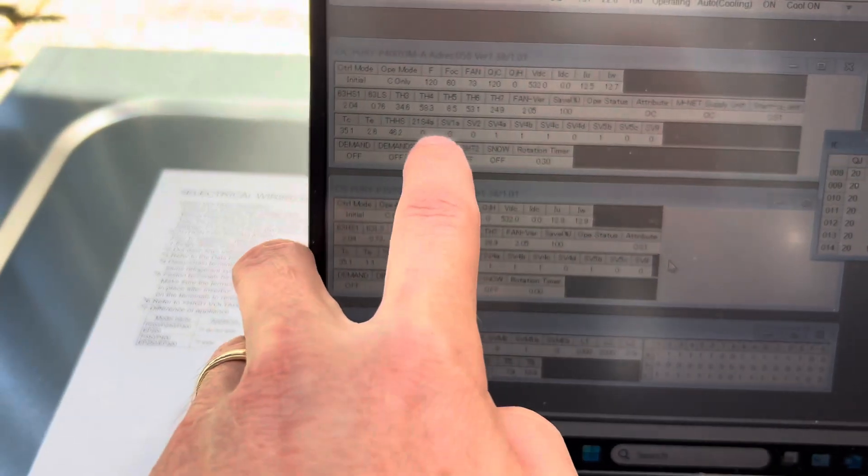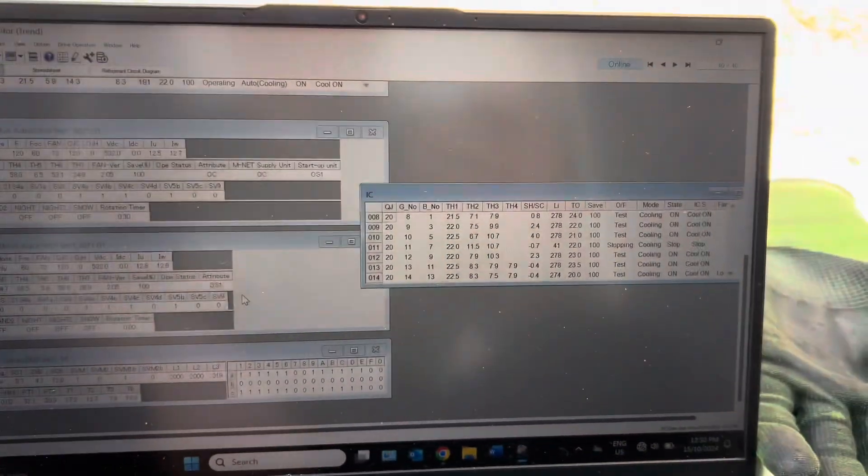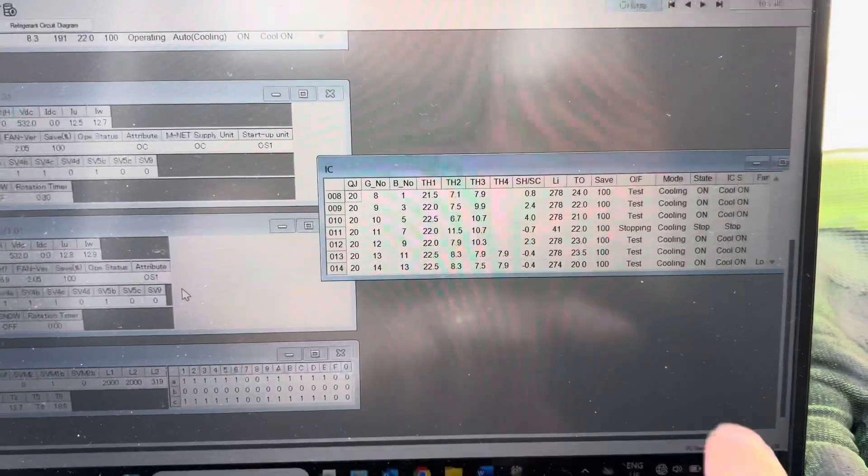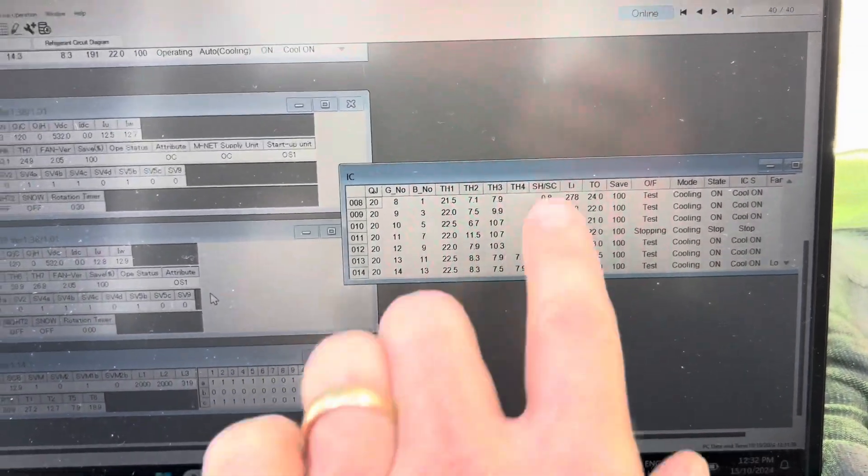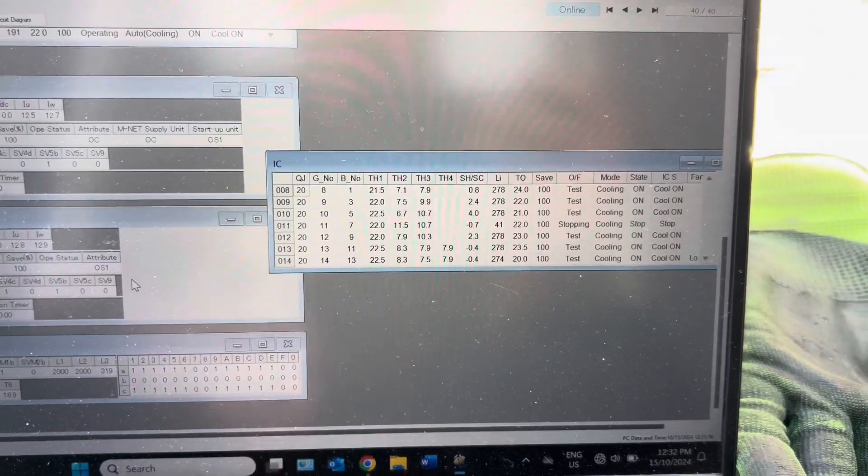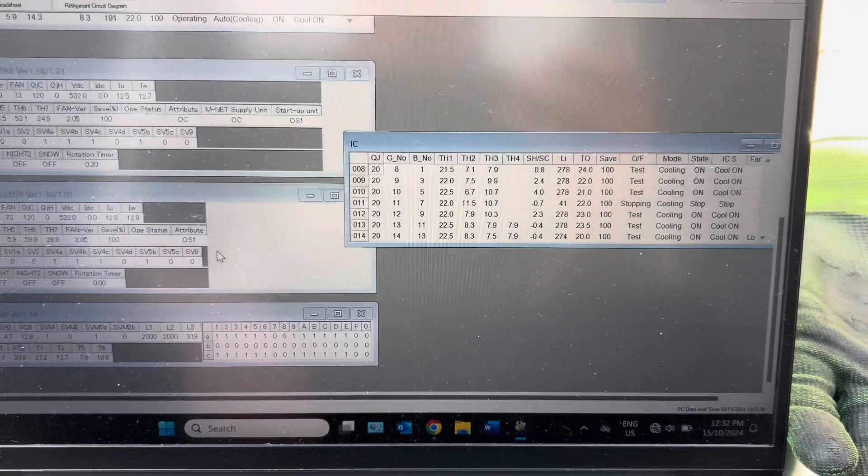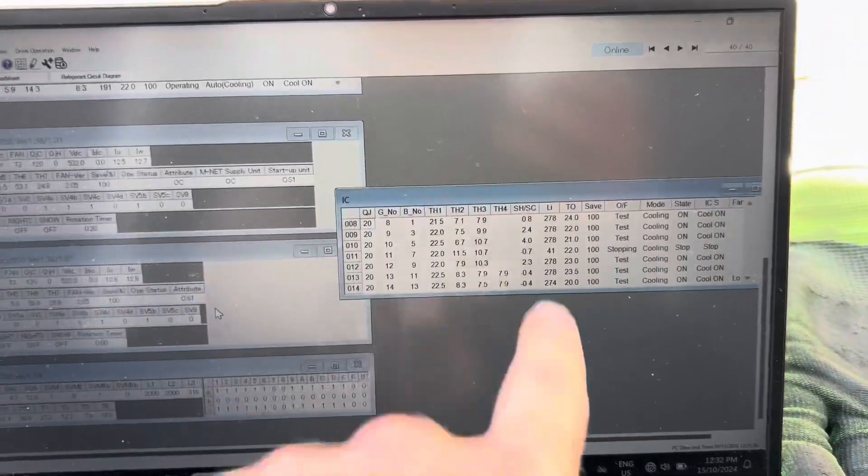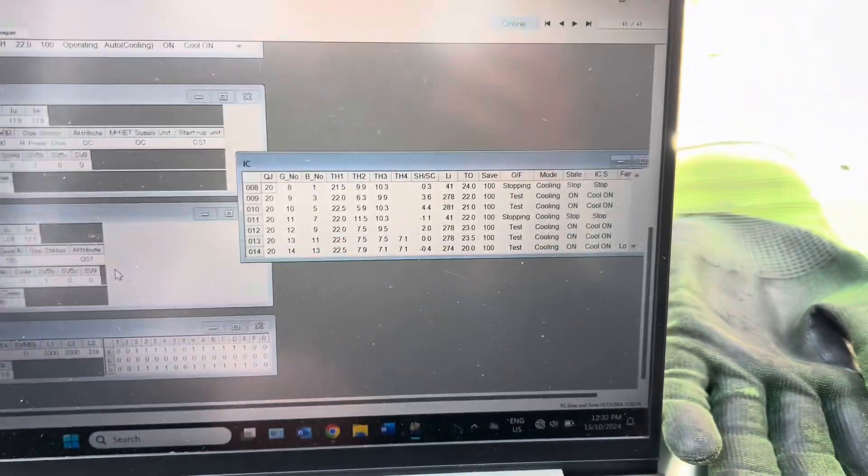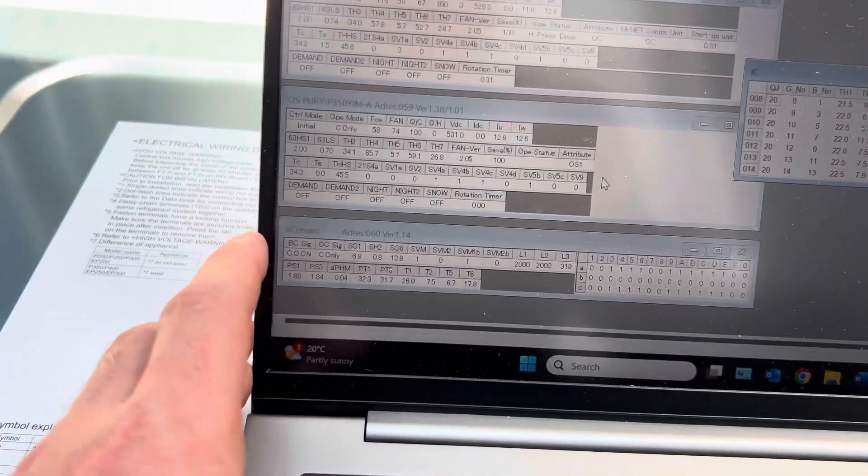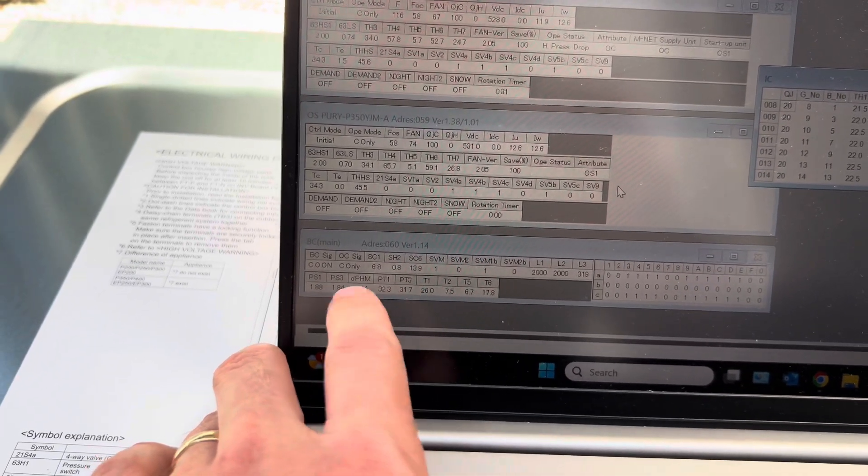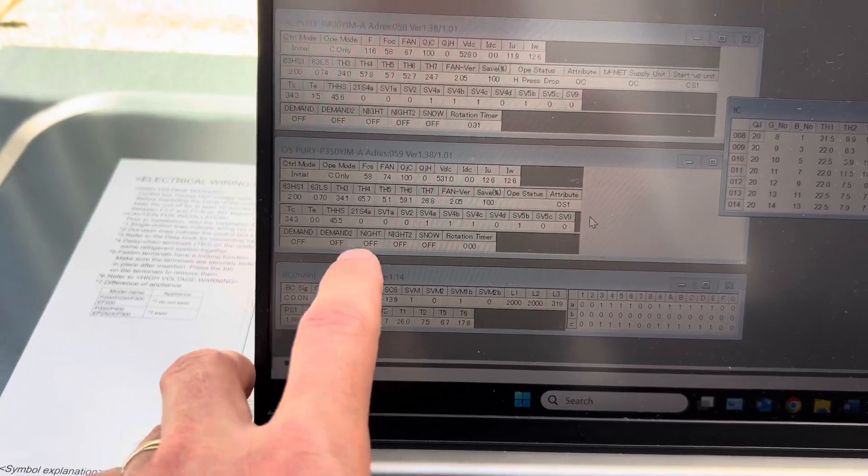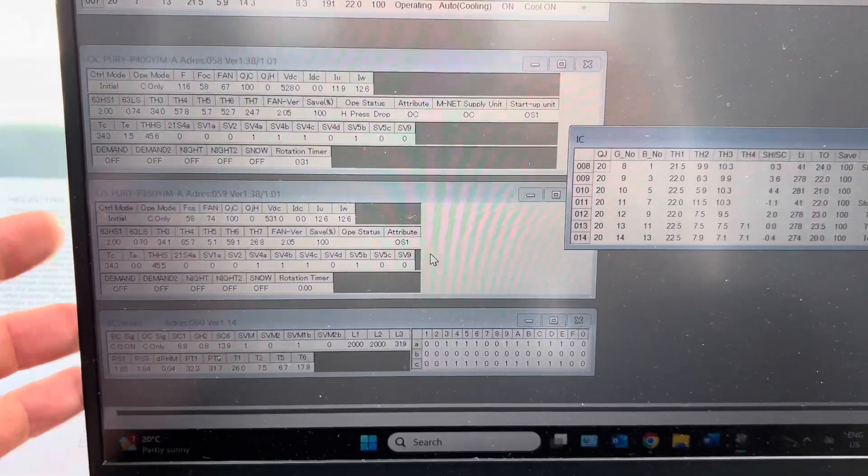You can see here TH5, which is our accumulated inlet temperature, not suction, just pre the accumulator. It's still reading quite high, but SV1A, which is the oil return solenoid, is still open, so usually you'll see that when it's quite high. You can probably hear that hissing noise, that's it. So for the first four minutes of operation that will be running, or if it feels like it needs to because our suction pressure drops. The system's still in initial mode too, so just waiting for it to come out of that before I fully start diving into the data that's coming through. Keeping an eye on it, everything looks okay at the moment, but yeah, we'll just wait for it to come out of initial mode. You can see now SV1A has closed, and TH5 has come down to 6.5 and 5.9. People are starting to get a little bit cold in there too, so they start shutting it down. Not uncommon, just in case anyone's wondering, to see these things for whatever reason—I don't really know why, but they do say zero superheat a lot of the time in a test cooling mode. I don't really know why, but it's not uncommon.